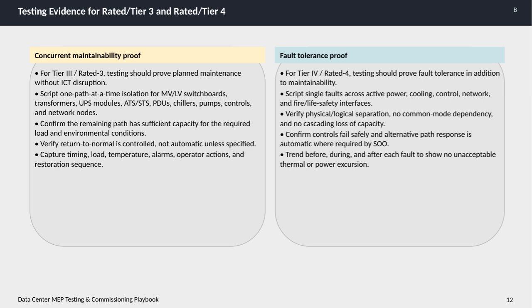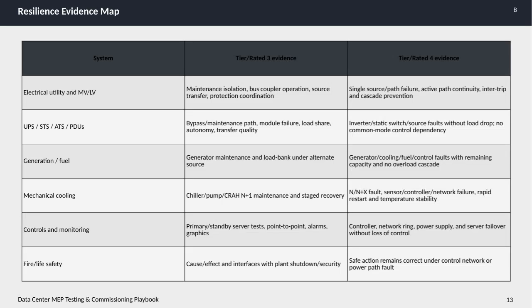In summary, these tests ensure that Tier 3 data centers can maintain operations during maintenance without disruption, while Tier 4 centers add an extra layer of resilience by demonstrating the ability to tolerate faults without service impact. Here we have a resilience evidence map that outlines the key testing and commissioning criteria for different systems in a data center, aligned with Tier 3 and Tier 4 levels of reliability.